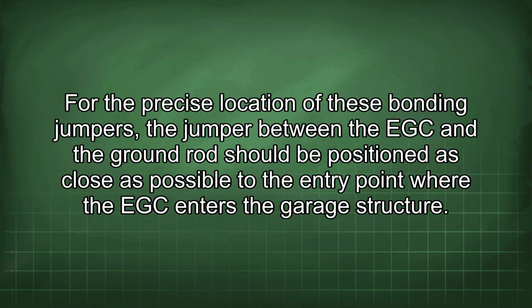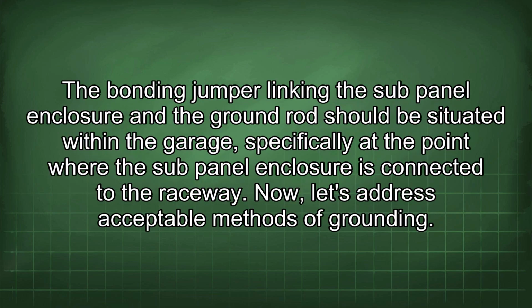For the precise location of these bonding jumpers, the jumper between the EGC and the ground rod should be positioned as close as possible to the entry point where the EGC enters the garage structure. The bonding jumper linking the sub-panel enclosure and the ground rod should be situated within the garage, specifically at the point where the sub-panel enclosure is connected to the raceway.